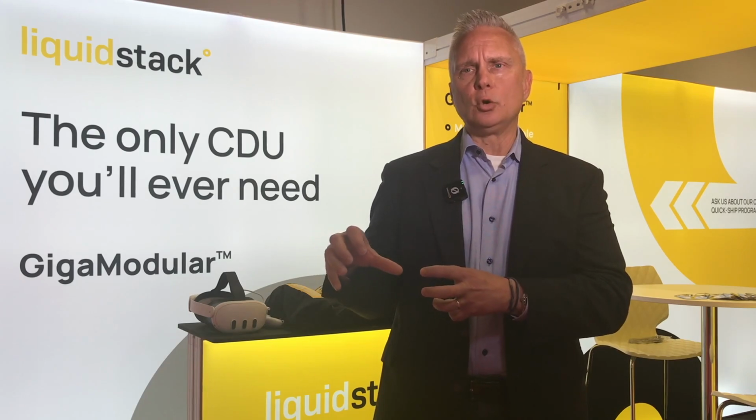Well, NVIDIA's already published their 3-year roadmap. And what we know is that chip TDPs are going to continue to increase. And rack densities reaching 600 kilowatts are already on the horizon. We know that TDPs will continue to increase beyond that. And so we see the implementation of two-phase liquid cooling solutions on the horizon as well. And this includes two-phase direct-to-chip as well as two-phase immersion, and then also the hybridization of direct-to-chip and immersion cooling technologies.